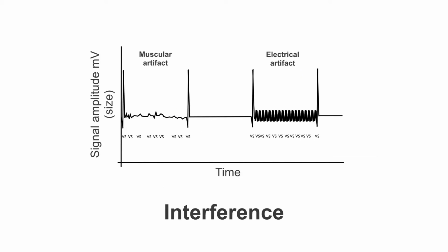Unfortunately, your pacemaker circuit will pick up more than just the heart's depolarization. In actual fact, there's two main types of artifact. Muscular artifact, which generally looks non-uniform and slightly irregular, and all that is the electrical activity generated by your other muscles in the body contracting, maybe your pectoral muscles or your biceps. You can see on this electrogram that the pacemaker has become confused and started to label this artifact as ventricular sensed events. To paraphrase, the device thinks that the heart is beating at every single one of these markers. And that can cause problems that we'll come on to later.